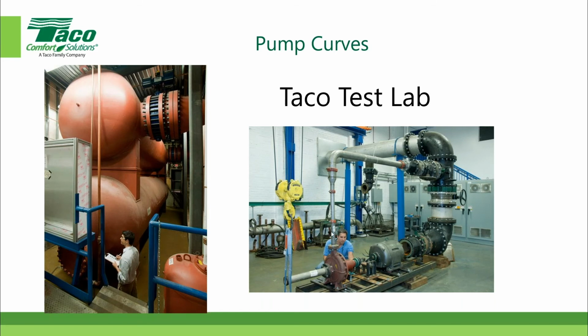There are 4 pieces of information that we need to collect in the test lab. We need to collect the flow in gallons per minute. We need to collect the differential pressure across the pump. That's the difference between the supply pressure and the suction pressure, or the discharge pressure and the suction pressure. And he needs to measure the horsepower.